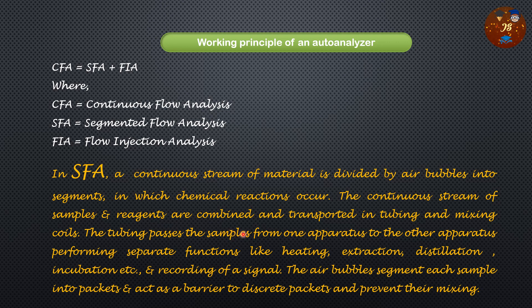The continuous stream of sample and reagents are combined and transported through tubing and mixing coils. The tubing passes the sample from one apparatus to another, performing separate functions like heating, extraction, distillation, and incubation. The air bubble segments each sample into discrete packets, acting as a barrier to prevent their mixing, so one sample can be separated into different analyzable packets.